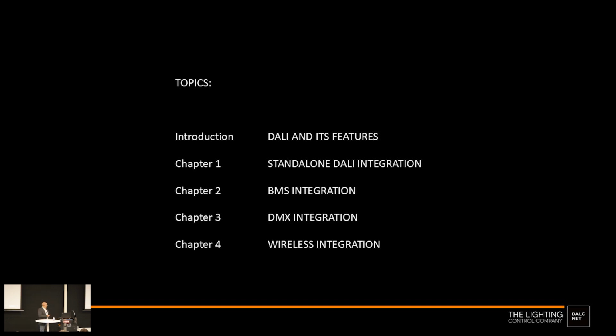DALI is a standardized protocol, but sometimes it's not a choice — sometimes it's forced by the power supply choice and availability, or by the light manufacturer or designer. In some cases we find integrations that require DALI to speak with other systems, because the light designer chooses luminaires based on aesthetics without considering that they have different protocols. Sometimes there are different control systems, like touch panels or BMS integrations, that don't speak DALI. We'll look at some examples.